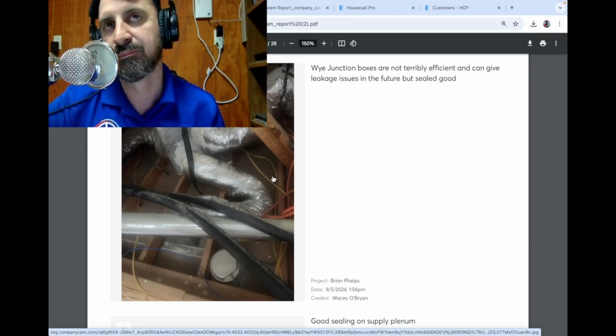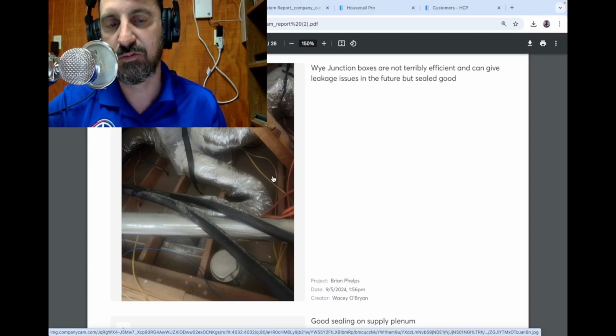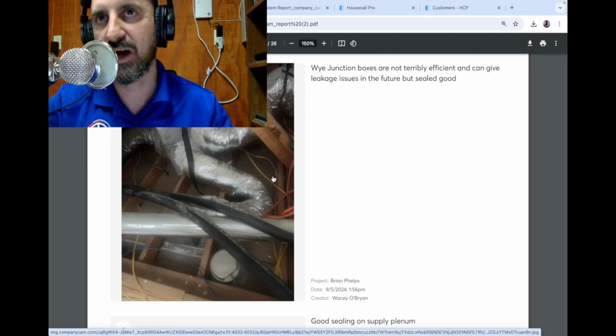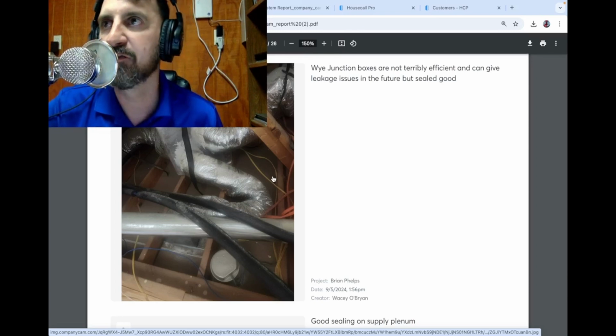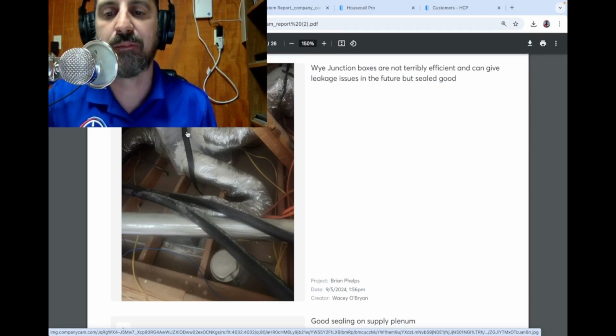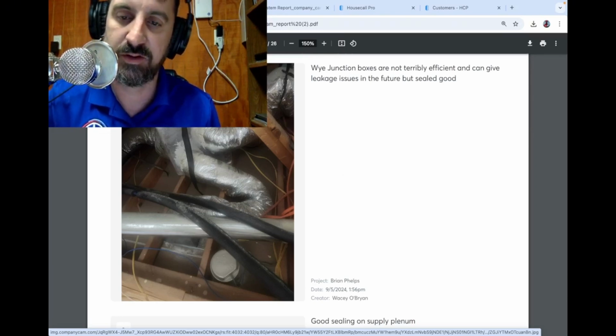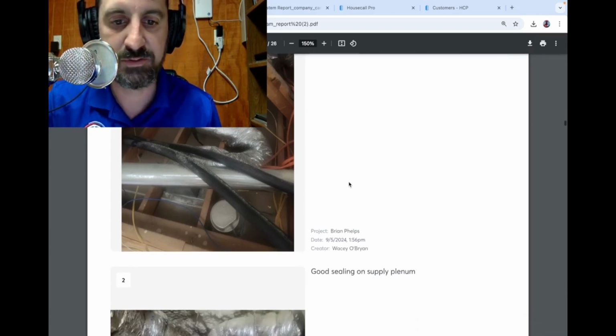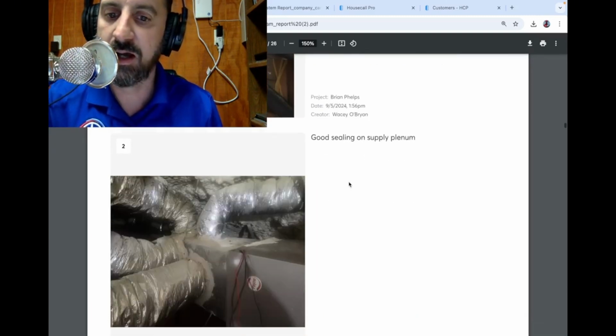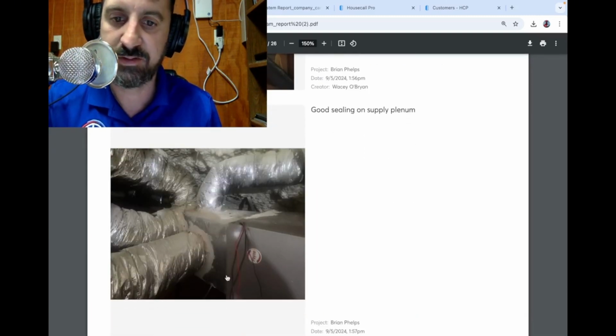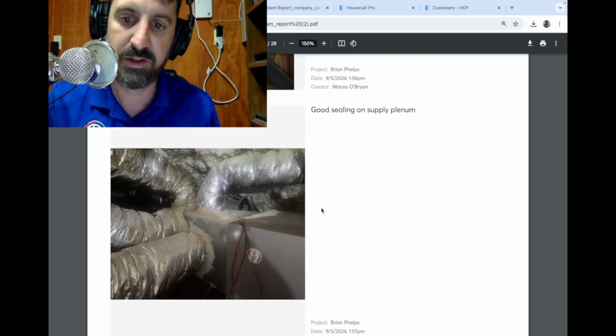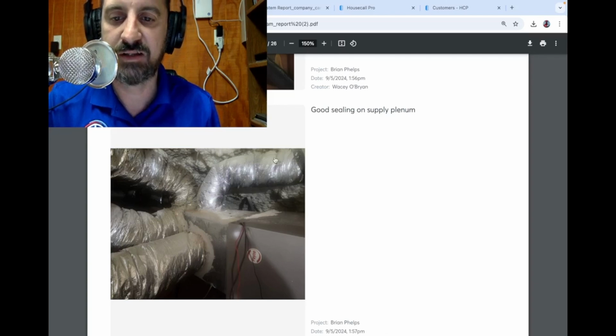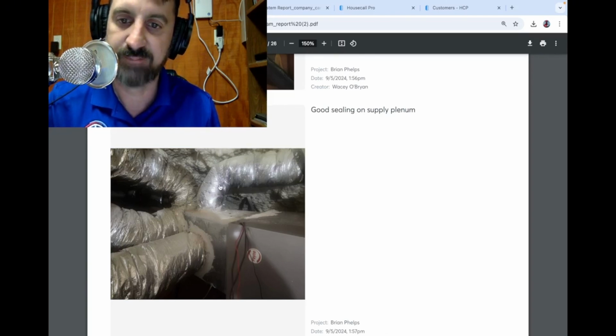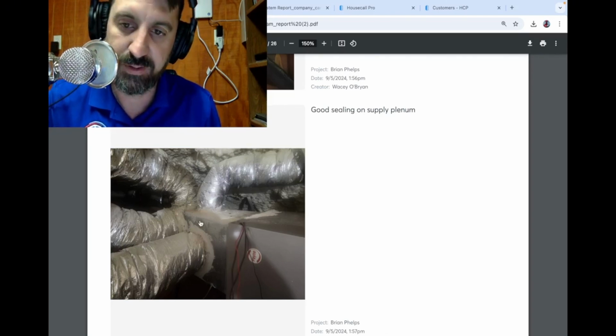Say we need two 7s in a room, we can run a 9-inch duct and Y it and get two 7s without having to make two holes off of our plenum, something like that. But this here is not my favorite type of junction box by far. Again, on the supply plenum, they masticed it up. It's sealed up good. Actually, even these 90s up out of the unit. I mean, this one's a little tight, but it'll pass air.